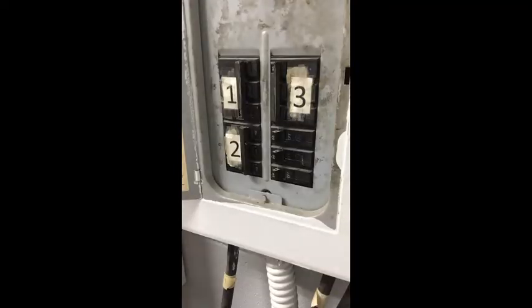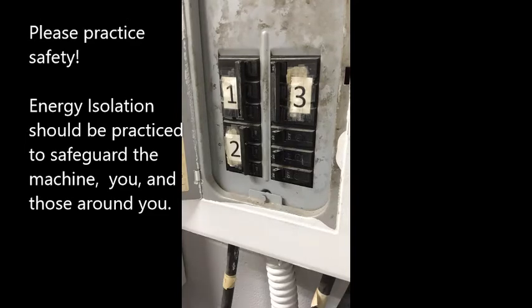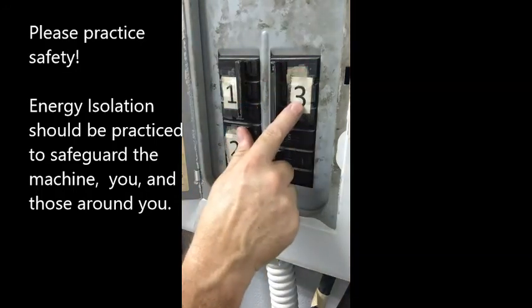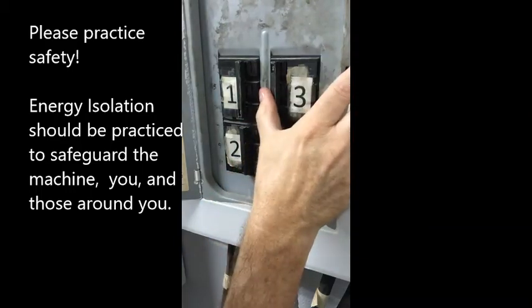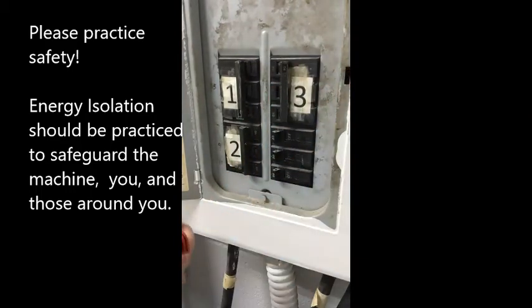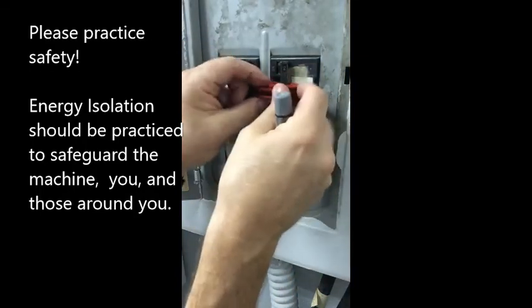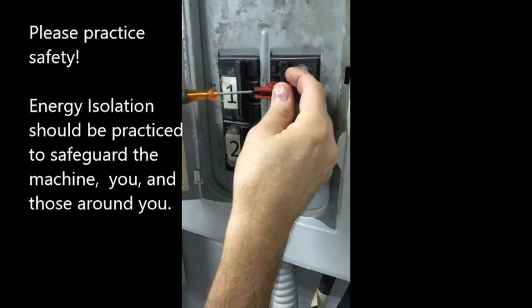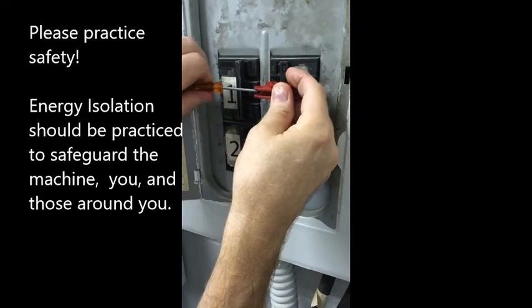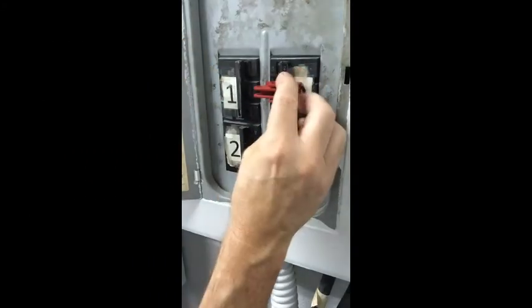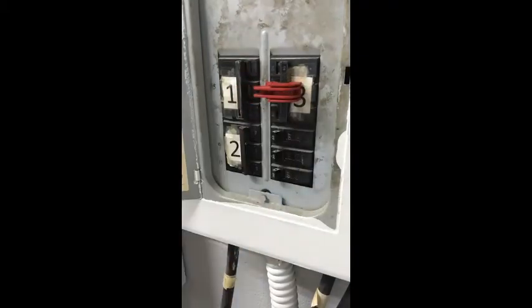Now these videos take into account that you have a basic electrical and mechanical knowledge, and one of the most important things you can do is protect yourself. So for lockout, tagout safety, I've tracked this back to this number 3 circuit, this unit that we're working on. We're going to turn this to the off position, and then I'm going to attach this lockout device, which just has a screw here that locks into here. Okay, once snugged and in place, that cannot be moved.